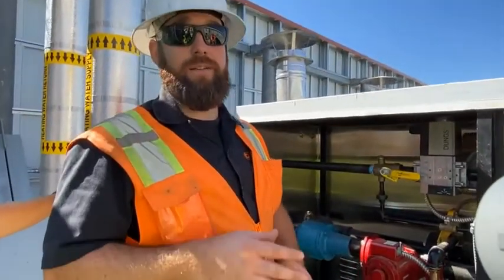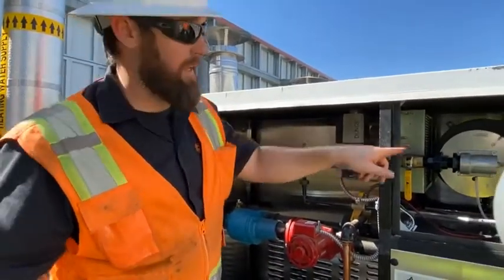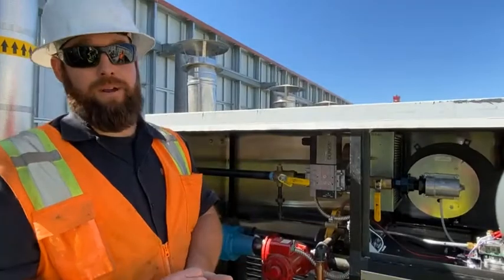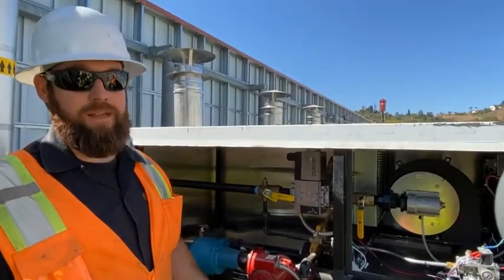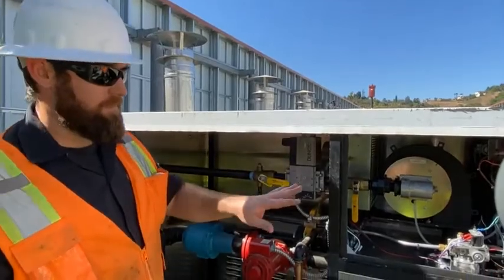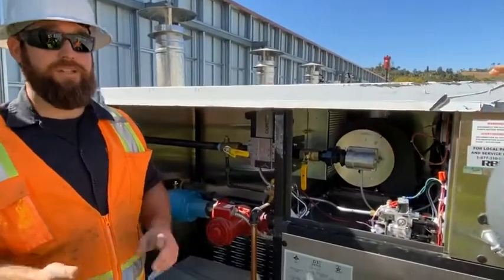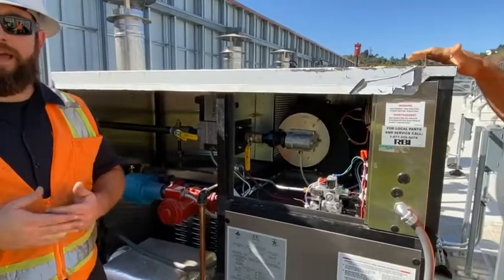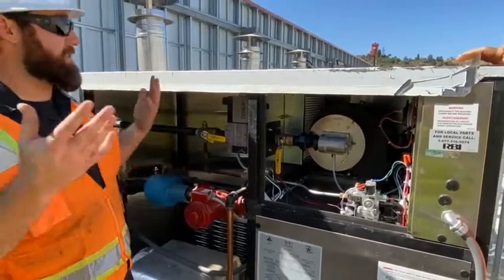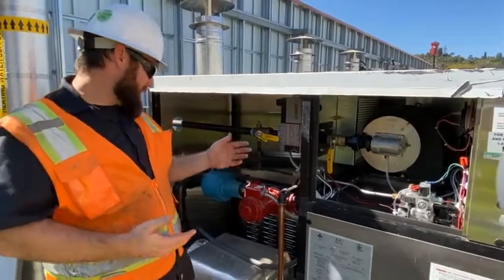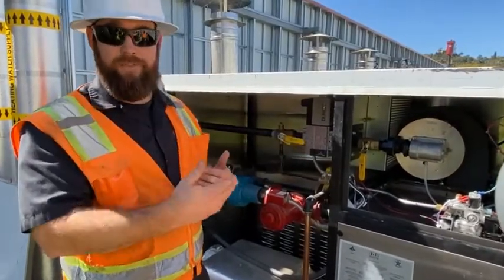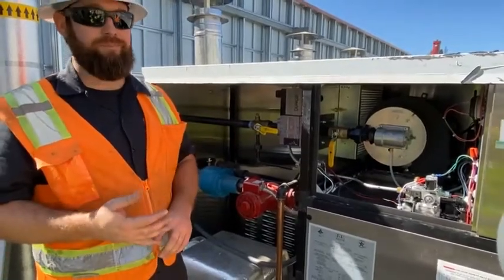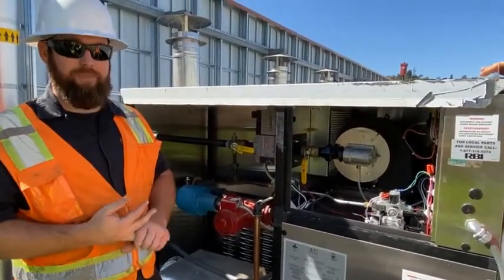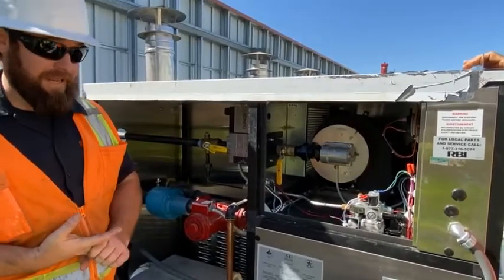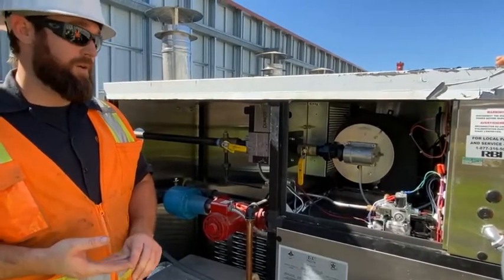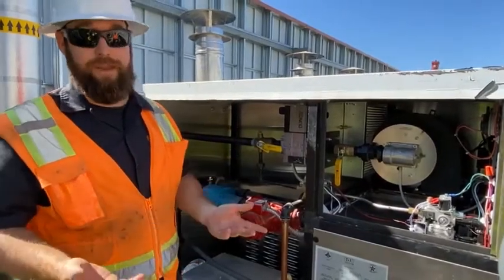If it gets too dirty and air's not getting through, that means dust and dirt is getting into this blower, down into the burner. If that burner gets clogged up, it's going to break and cause a lot of issues. So I would recommend checking that at first every couple months, and then get a game plan on how these react, because you're outdoors, right? So it's going to be pulling. It's kind of covered here, so that's nice. Hopefully not as much dust and dirt will get in, but you want to know your units. So I would say check it every couple months, and then definitely replace the filter every year, depending on how dirty it gets, maybe every 6 months.